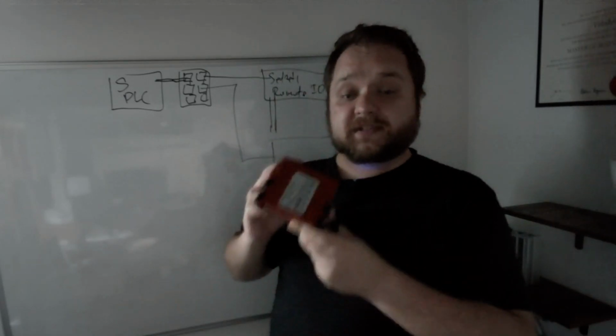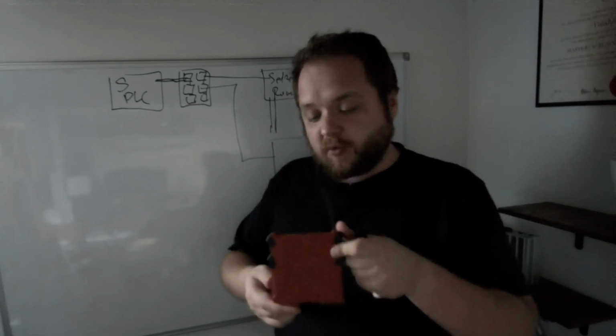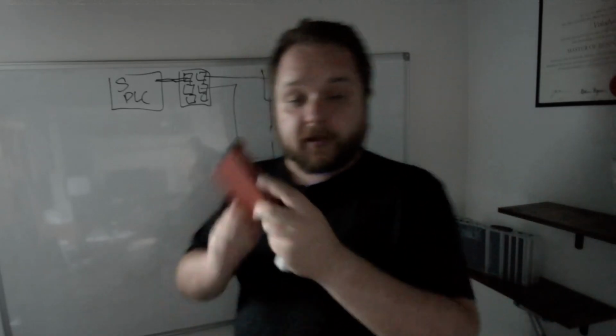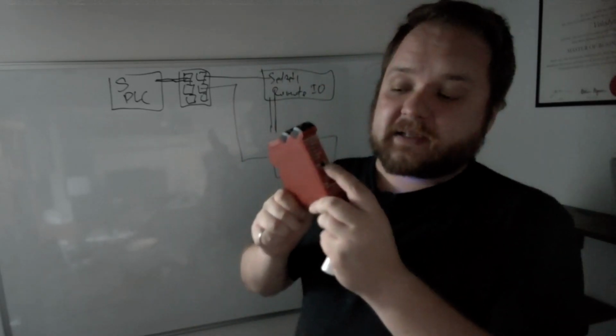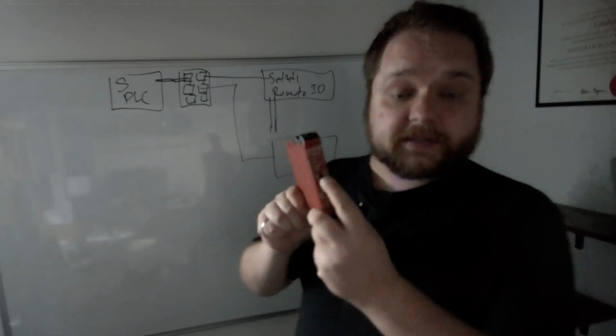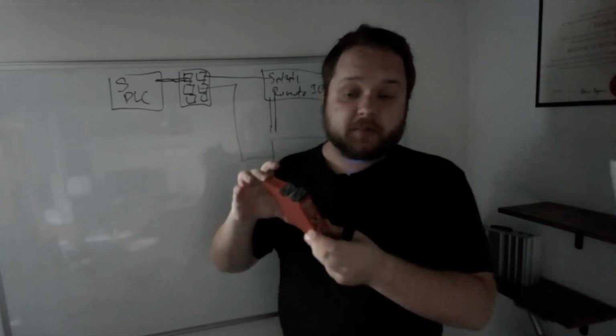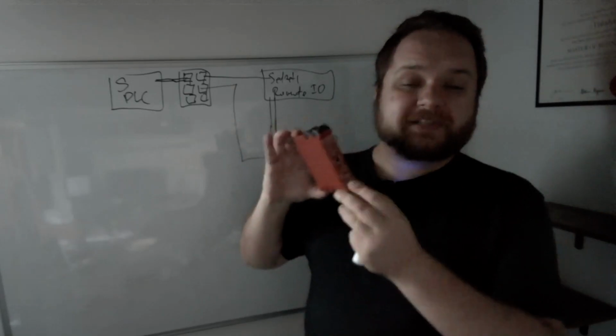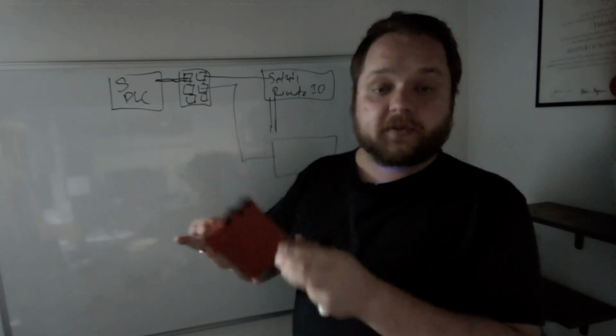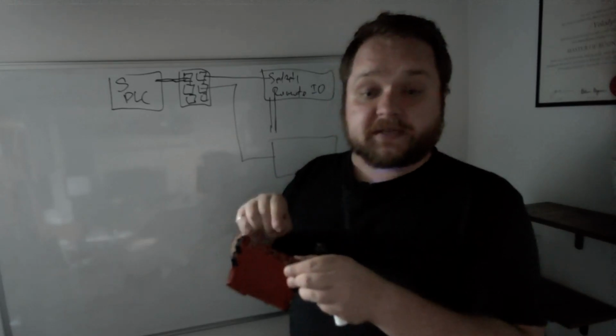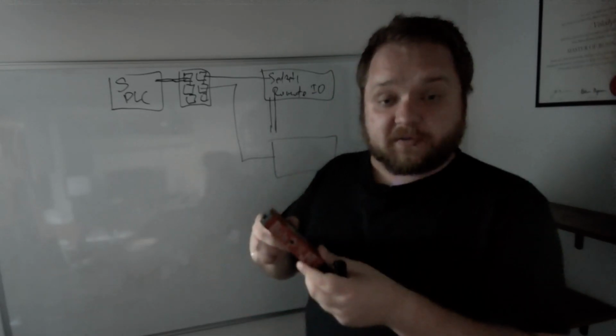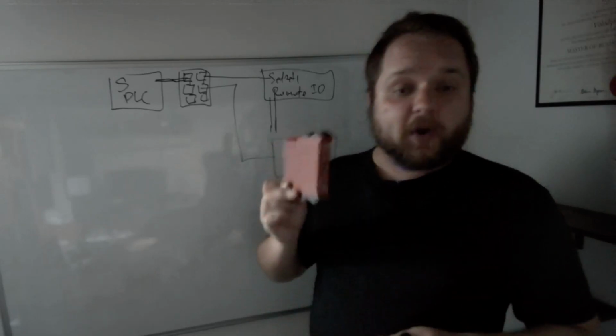The last item I will mention is that different lines of safety relays are going to have different features in place, and they have gotten quite complex themselves. So you will notice that not only is this relay dual channel, it also has different features as indicated by the selector switch on the front. And so it's very important to read the documentation, because with this relay, you simply cannot assume, as you see it on the panel, that it's going to have the exact same functionality from one relay to the other, because it can be programmed via the dial in the front. These relays are also quite a bit more sophisticated.